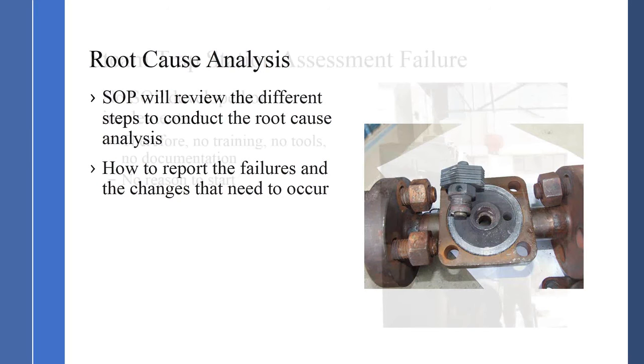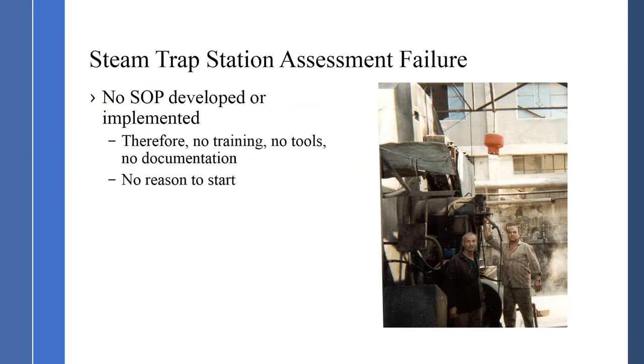Root cause analysis is part of the SOP — taking the steam trap apart, visually inspecting it after detecting a failure mode, and documenting the failure and correction method. Not only what failure occurred, but what changes need to occur to prevent further failures at that steam trap station. Root cause analysis must be done with each steam trap in failure mode to understand what caused the failure and institute changes to prevent further failures. One of the most common assessment failures is no SOP being developed or implemented — therefore no training, no tools, no documentation — and if you don't have those, there's no reason to start.